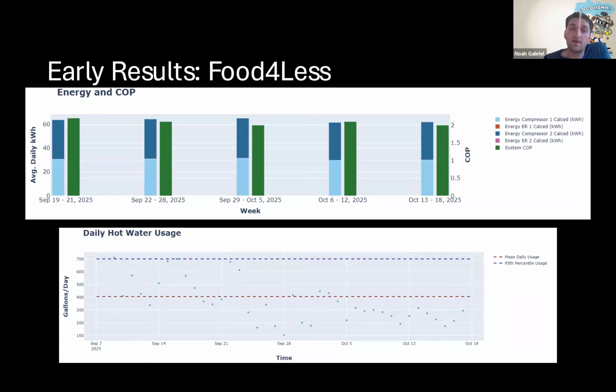Both of these sites have quite a nice setup in that they're co-located near a bunch of cooling equipment, so there's a lot of waste heat flowing in. The temperature is sticking between 70 and 80 in these big rooms. So generally speaking, we would expect performance to be even a little bit higher, but we'll do some further investigation into the install and potential reasons why that could be happening, because we're not seeing a whole lot of electric resistance use either. So it could just be the variable demand here on the system.